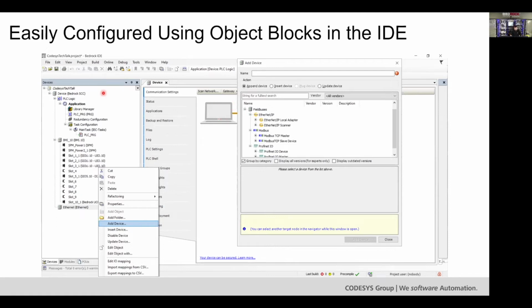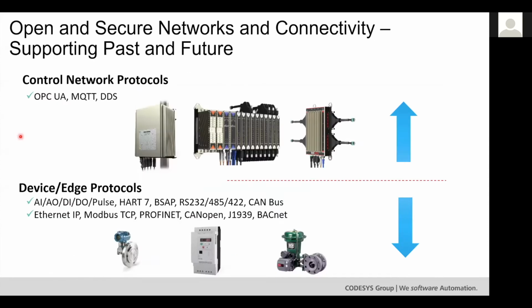Do you have any comments, Marcus, about implementing field bus or supervisory? Yeah, just being familiar with the CODESYS platform, it's very intuitive, and being able to add the protocol devices. And just a comment on the previous slide, we use quite a bit of OPC-UA and Modbus TCP, and also the HART field device protocol has really allowed us to standardize on our analog sensors quite a bit, with a lot of diagnostic information, and that's been pretty beneficial.